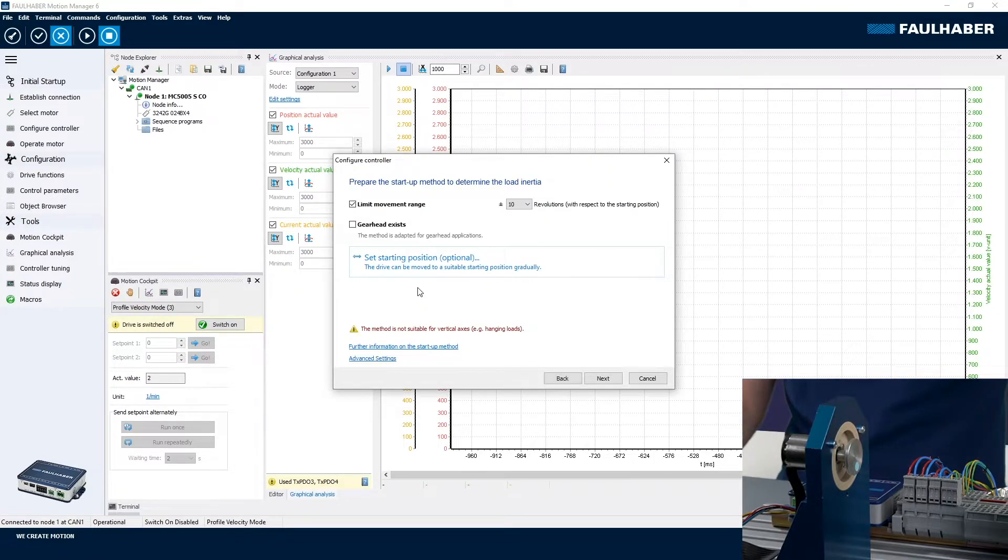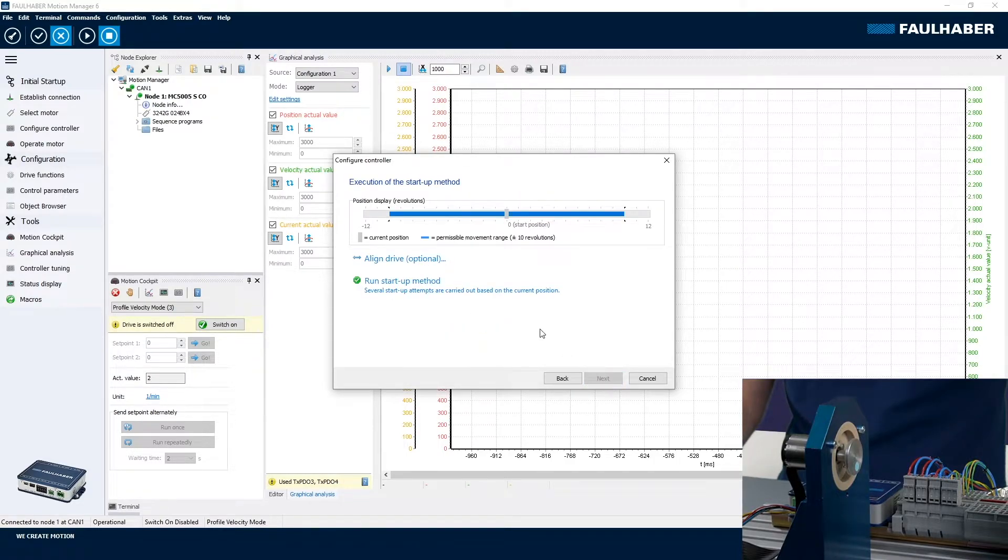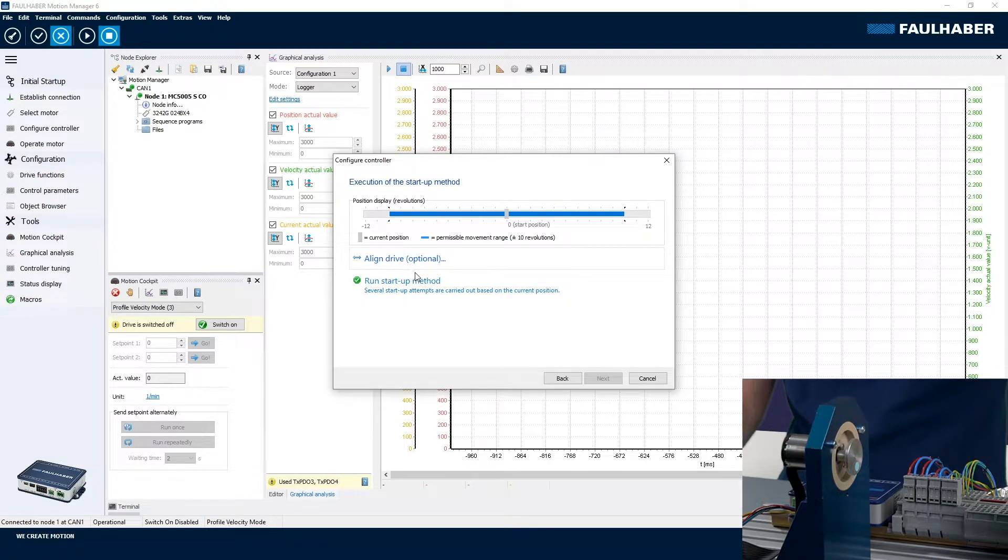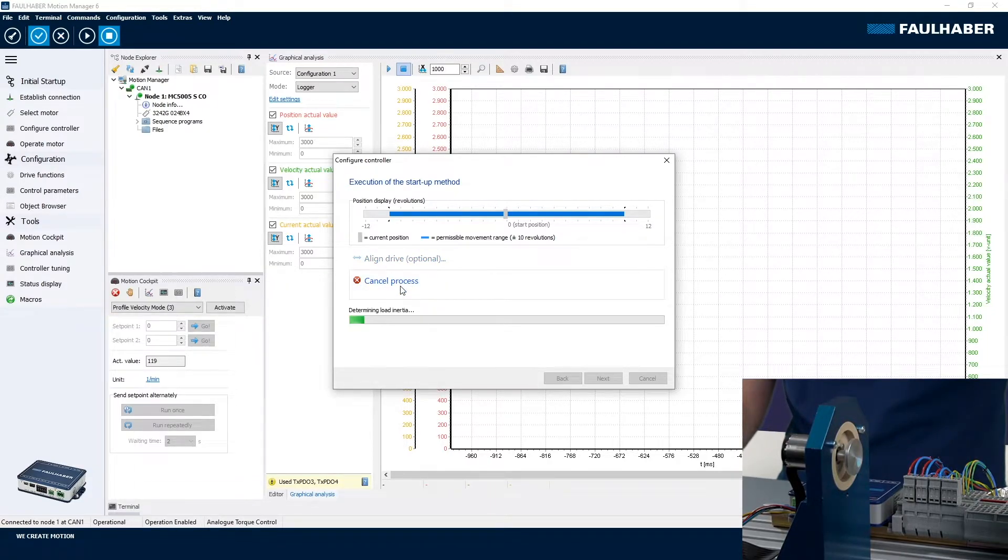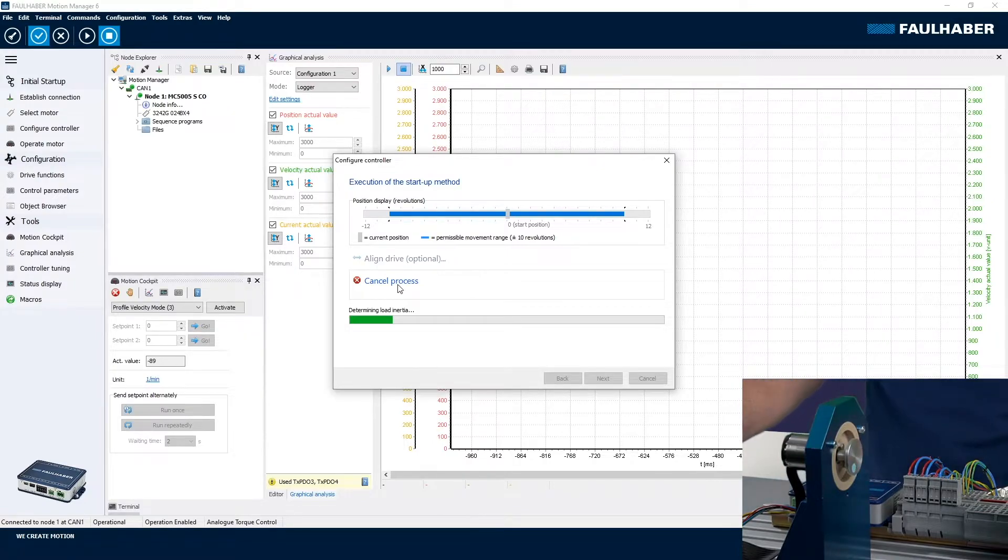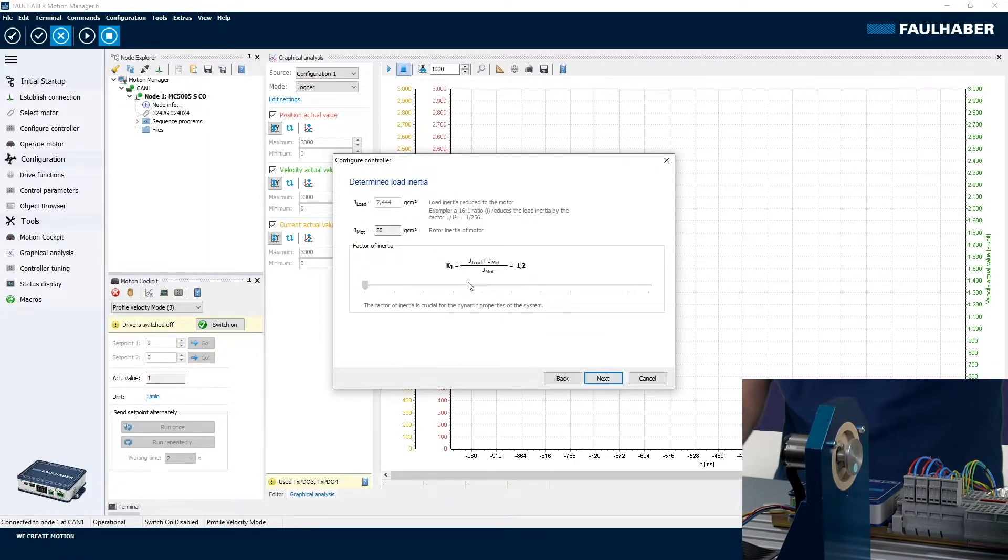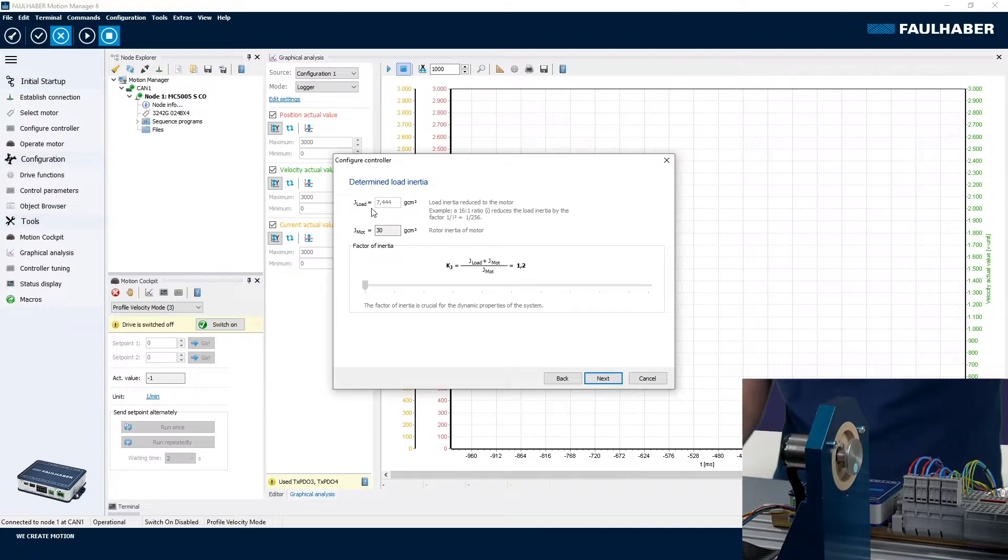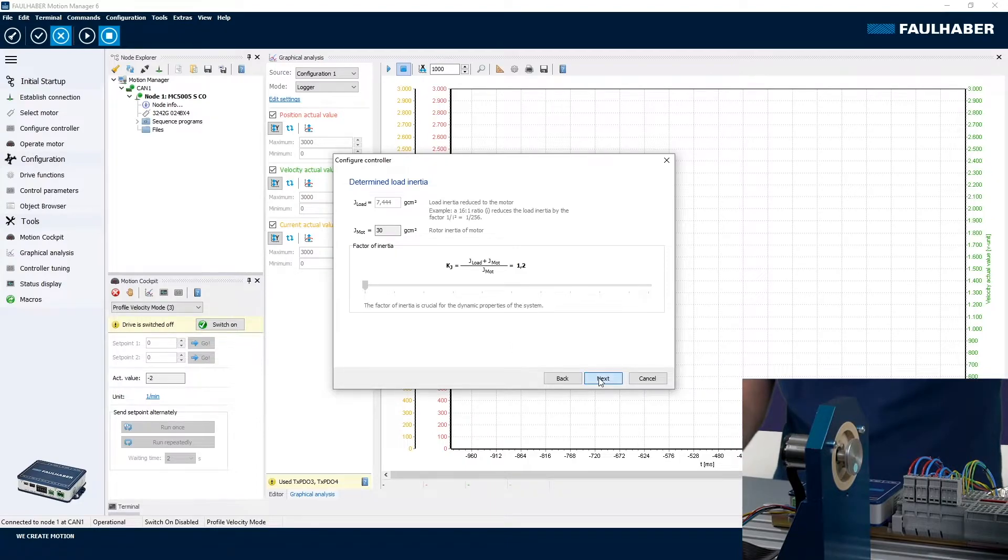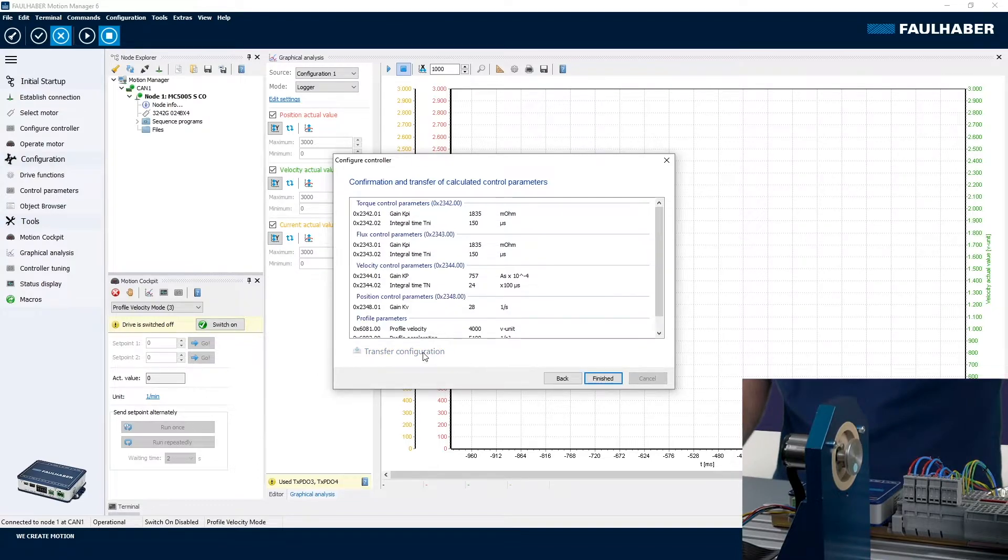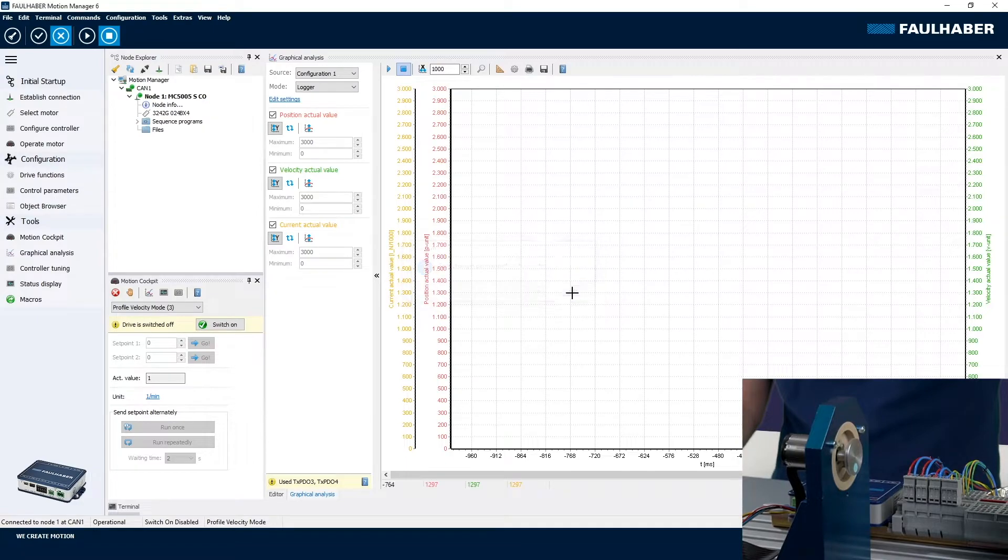So start with identification. We could even move the motor in the middle of the possible range here, but that's not necessary here with the free running disk, and then run the startup method. So we got some steps which are applied to the motor here, and it's moving. Next page is the summary. So here is the inertia of the motor and that's what has been identified for the disk, and that's reasonable. It's a pretty small disk compared to the motor, but that's sufficient here for the general approach. We get a summary of all the parameters and download them to the driver and are finished here.